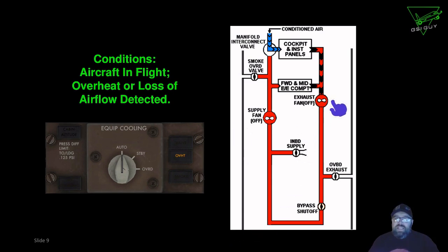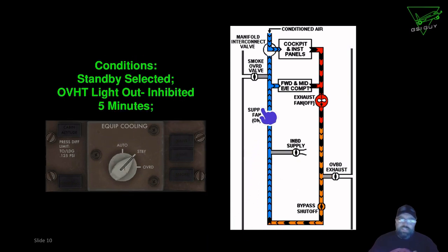Okay, so let's say that this was the reason I'm overheating. The exhaust fan failing is why I'm overheating. I go to the standby position. It turns my supply fan on in this case. So now the theory is the conditioned air is going to come in and it's going to get blown into here. But this fan being on is going to create a pull, and it's going to pull that air through the system like it always would.